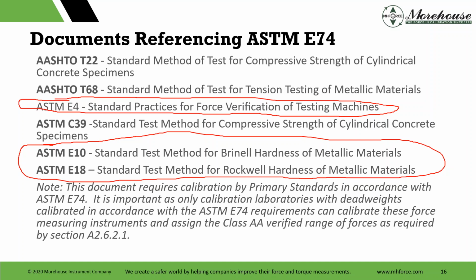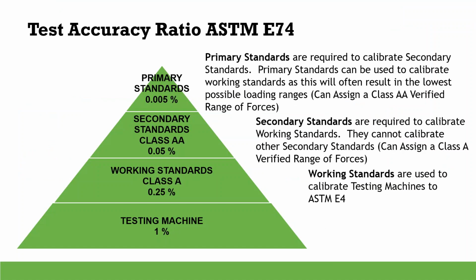Basically the call out is this: this document requires calibration by primary standards in accordance with ASTM E74. It is important, as only the calibration laboratories with dead weights calibrated in accordance with ASTM E74 can calibrate these force measuring instruments and assign a Class AA verified range of forces, as required by Section A2.6.2.1. So basically, the standard says you need to have your instruments calibrated in accordance with ASTM E74 by dead weights for verification. That's essentially what's going on there, and I would suggest reading E10 and E18 for more details. They both call out the Class AA verified range of forces.